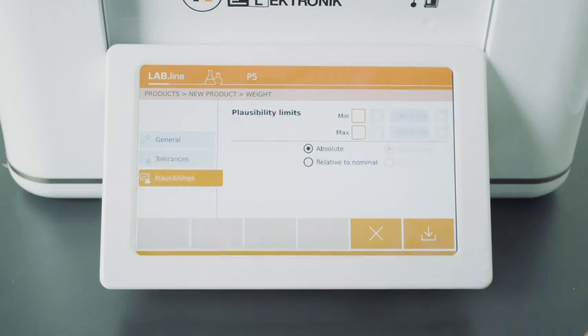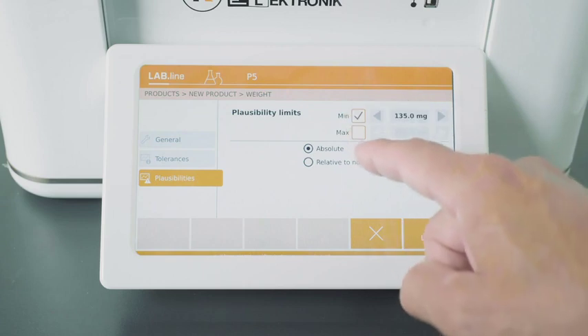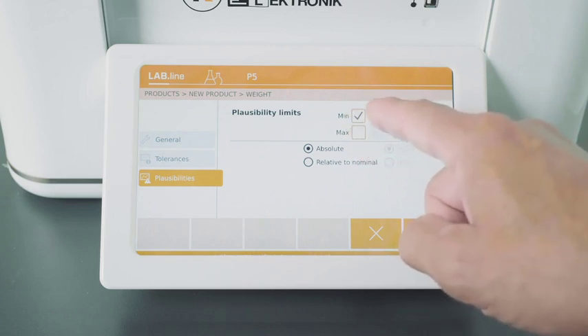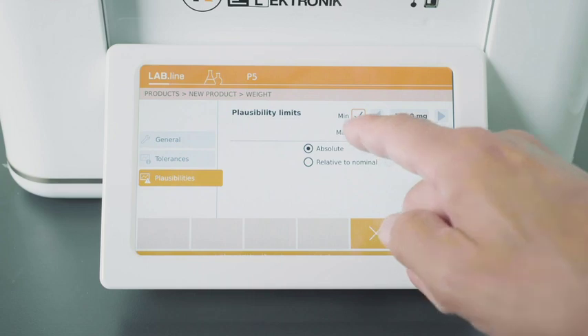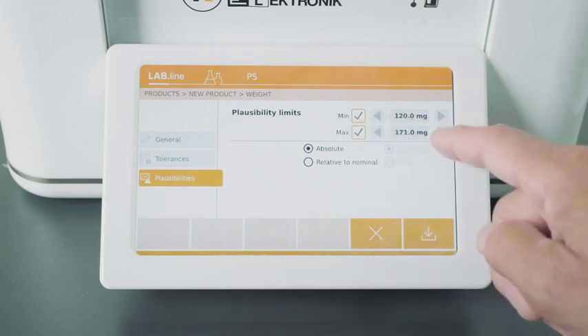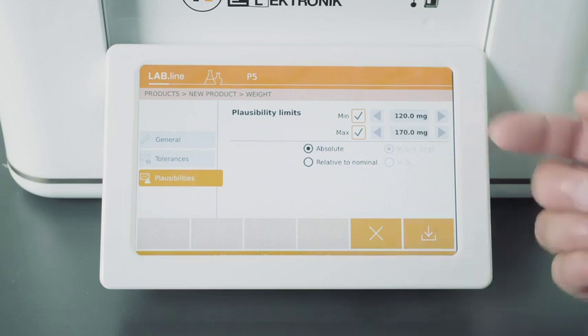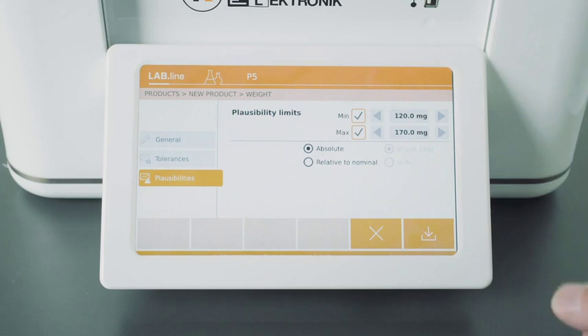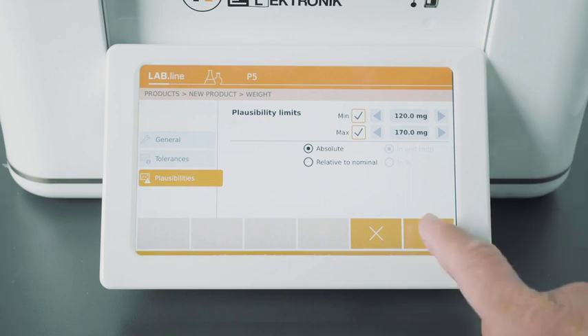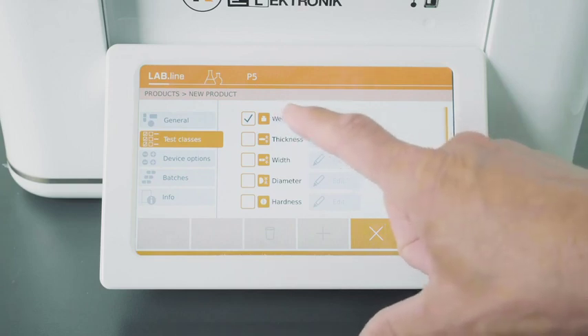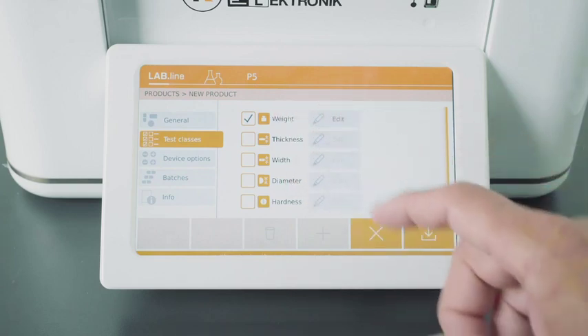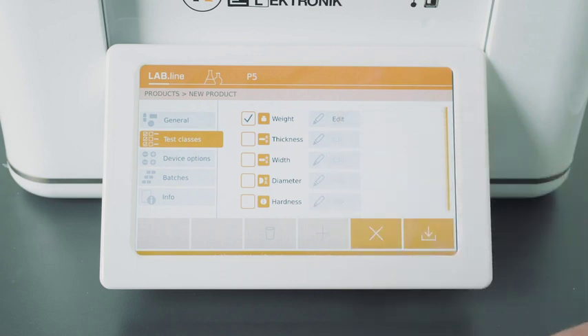In addition to that, we can also set up a plausibility limit right here, for example as 120 milligram, the lower one, and the maximum, for example 170. This means all values that are measured outside this range will be ignored and do not go into the statistics. This is a good feature to avoid false measurements in case an operator puts two tablets in one chamber. So we store these values, and now we can repeat the same procedure for thickness, width, diameter, hardness.